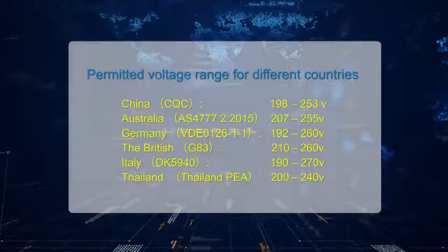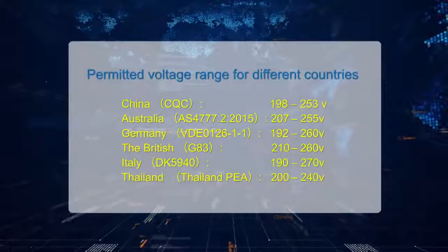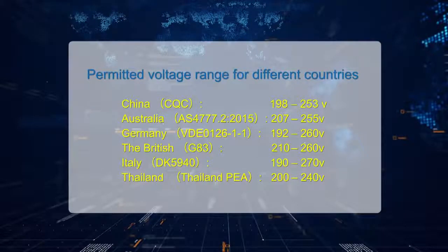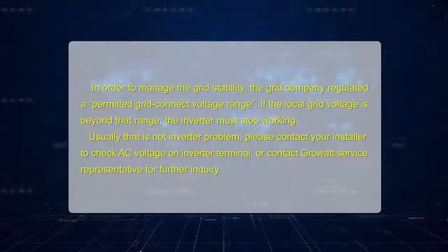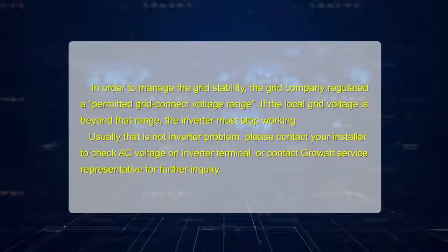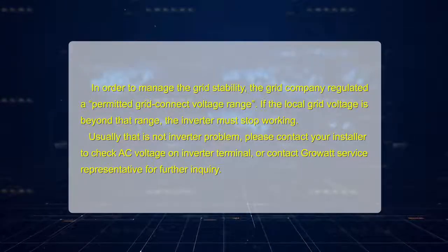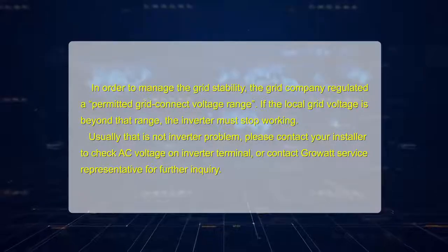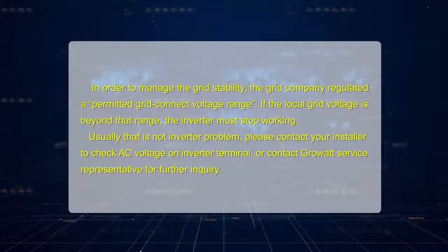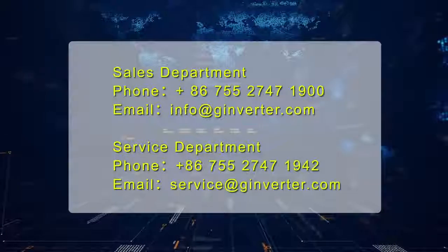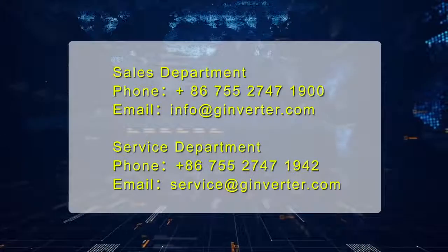In order to manage the grid stability, the grid company regulated a permitted grid connect voltage range. If the local grid voltage is beyond that range, the inverter must stop working. Usually, that is not inverter problem. Please contact your installer to check AC voltage on inverter terminal, or contact Growatt service representative for further inquiry.